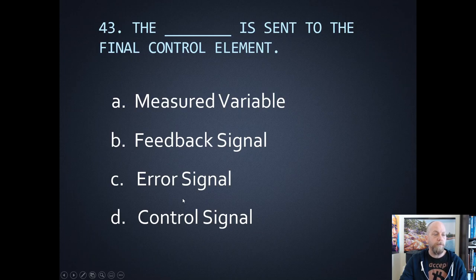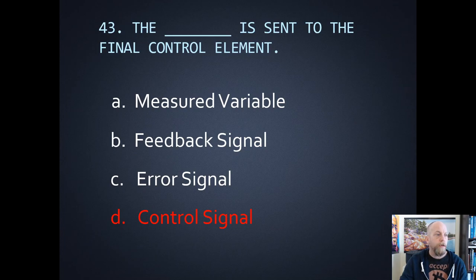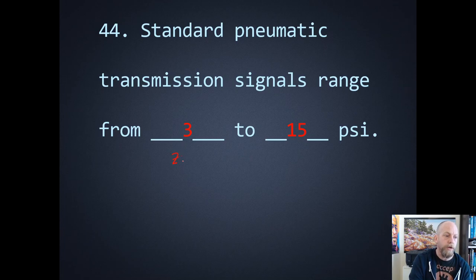Now completion questions. Which one is sent to the final control element? The final control element is the actuator out in the field — the valve, the motor, or the heater. The control signal is the one that was sent out to the field. Number forty-four: standard pneumatic transmission signals — that is the air signal sent to a larger valve to open and close it — the range there was 3 to 15 psi, with 3 corresponding to the zero and 15 corresponding to the span.